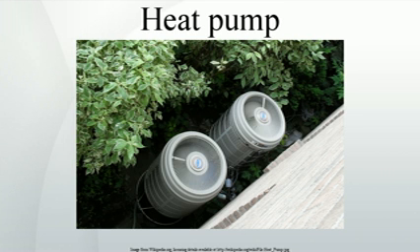That is, 1 joule of electrical energy will cause a resistance heater to produce only 1 joule of useful heat, while under ideal conditions, 1 joule of electrical energy can cause a heat pump to move much more than 1 joule of heat from a cooler place to a warmer place. Note that an air source heat pump is more efficient in hotter climates than cooler ones, so when the weather is much warmer the unit will perform with a higher COP, as it has less work to do. Conversely, in extreme cold weather the COP approaches 1. Thus when there is a wide temperature differential between the hot and cold reservoirs, the COP is lower, worse.